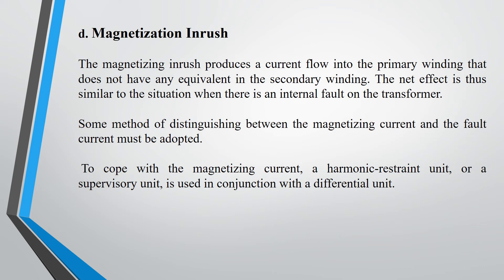The fourth consideration is magnetization inrush. When a transformer is given the supply, a magnetizing inrush current flows into the primary winding whose equivalent is not present in the secondary winding, as this magnetization inrush current is used to magnetize the iron core. The net effect of this will be considered as an internal fault by the differential protection. Thus, a unit must be added with the differential protection that can distinguish between the magnetizing current and the fault current. Generally, a harmonic restrained unit or supervisory unit is used with the differential unit to cope up with this magnetizing inrush current.